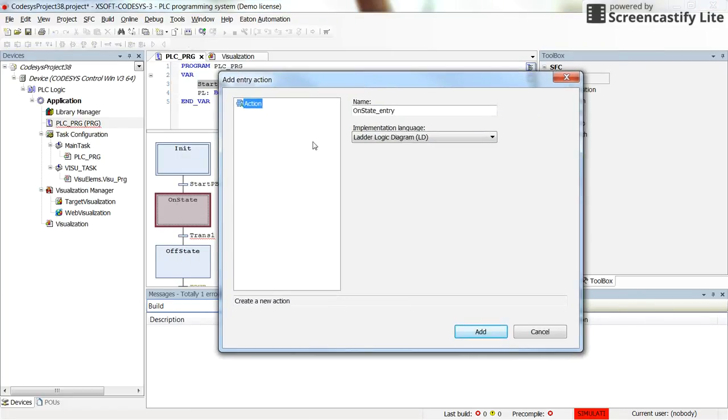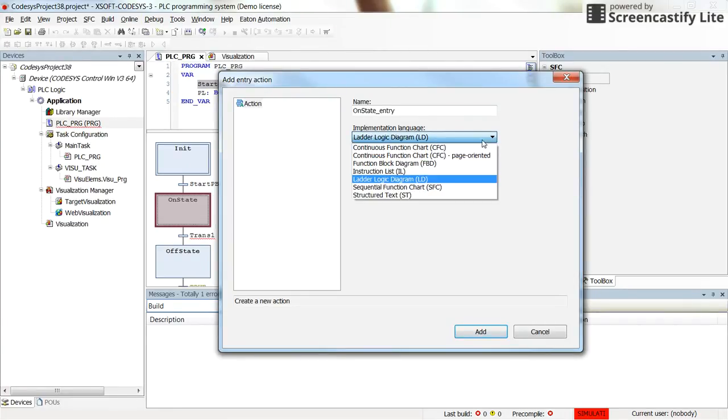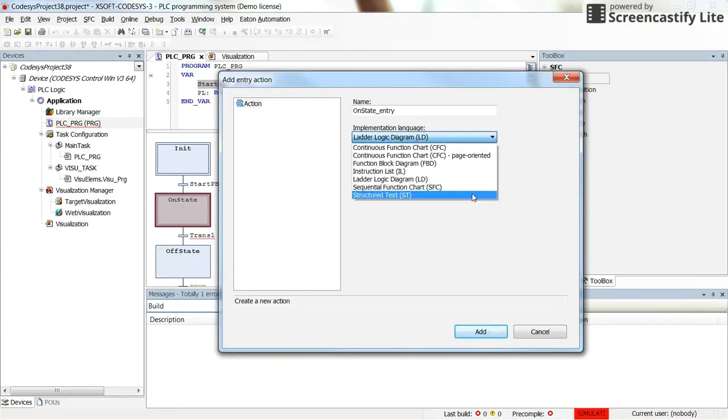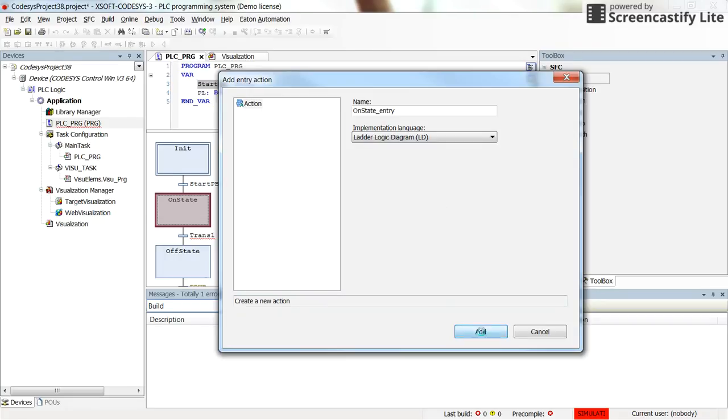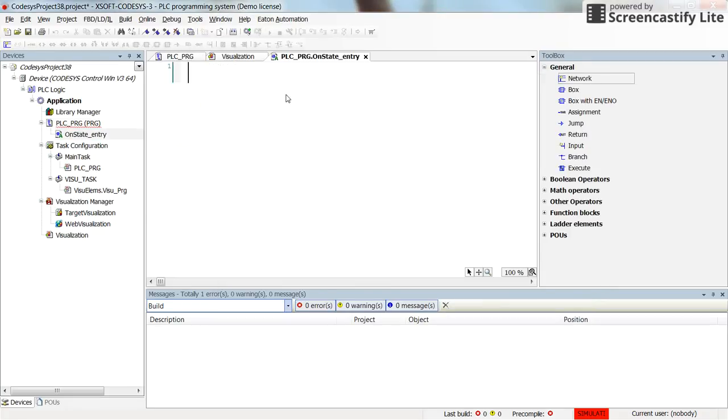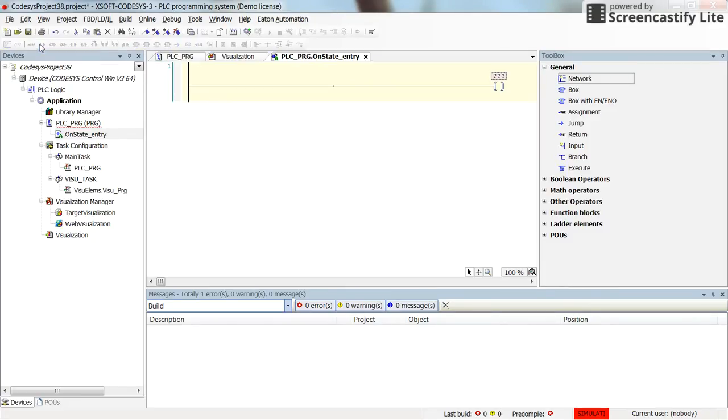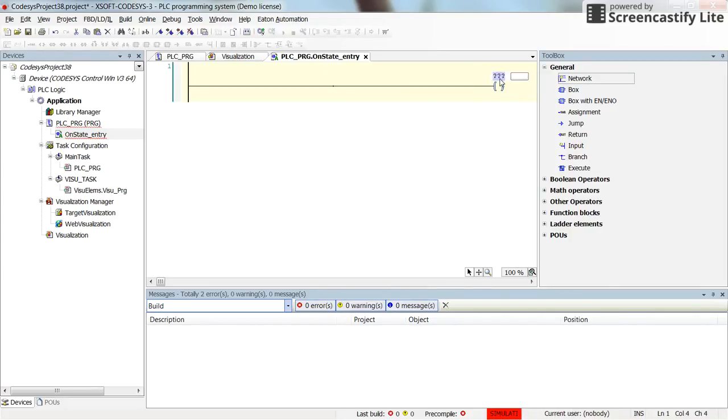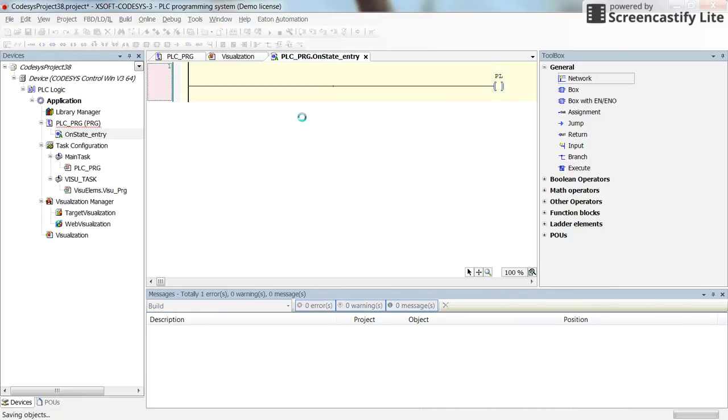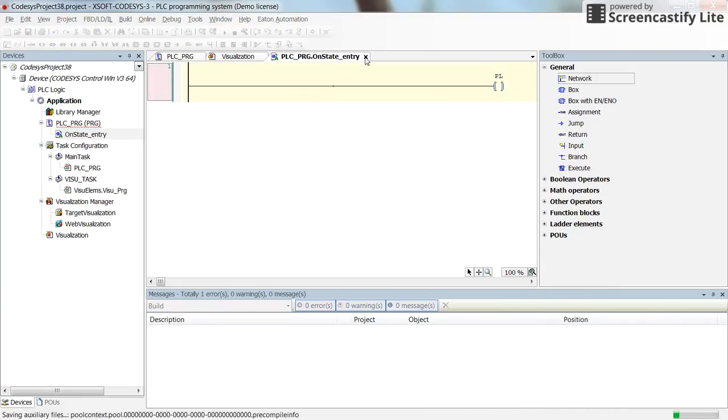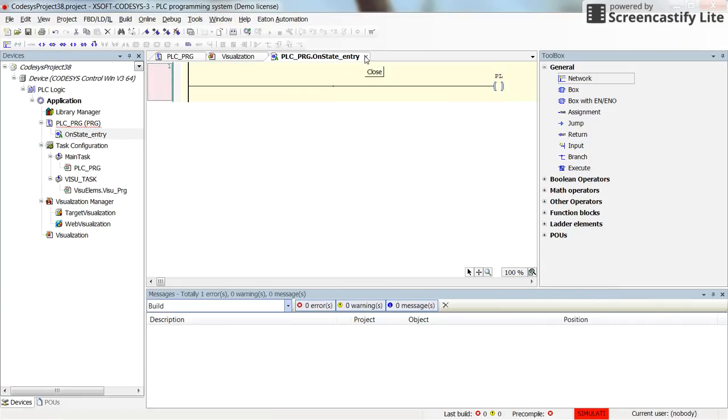So by default, it's called on_state_entry. You can change it if you wish. I'm going to keep it like that. And here we can select the language for the implementation. Any of the standard languages. To make it simple, I'm going to use the ladder logic for now. Alright, so here I want to turn on the pilot lamp. I can insert the coil, connect it to the line and then determine the variable PL. So it will be turned on automatically. And then I can close this.